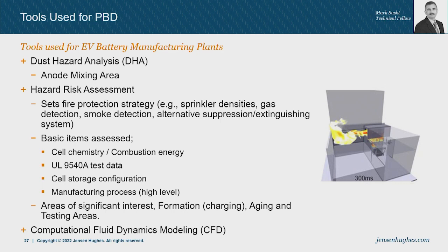Jens talked about the risk hazard analysis, so I'm just going to touch on that a little further. That is probably one of the key items that we think is necessary when you're working in these environments. That risk hazard analysis is really what's going to set your game plan for the rest of the design. It's going to set the design criteria for the sprinkler system, for any smoke detection systems, any gas detection systems, any venting or ventilation that you may need. So once that's in place, you're locked in. You have your protection strategy specifically for your protected hazard.